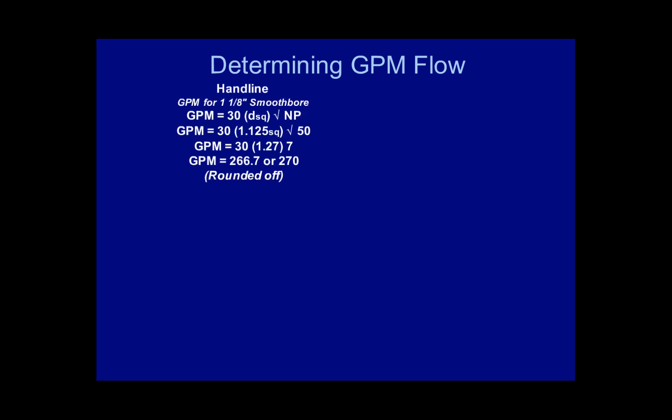Determining GPM Flow. Let's look at an example for a handline. To determine the GPM for an inch and an eighth smoothbore tip, we're going to use the formula GPM equals 30 times diameter squared times the square root of the nozzle pressure. GPM equals 30 times 1.125 squared times the square root of 50 for a handline, which equals 30 times 1.27 times 7, equaling 266.7, or rounded off to 270 GPM for an inch and an eighth smoothbore tip.